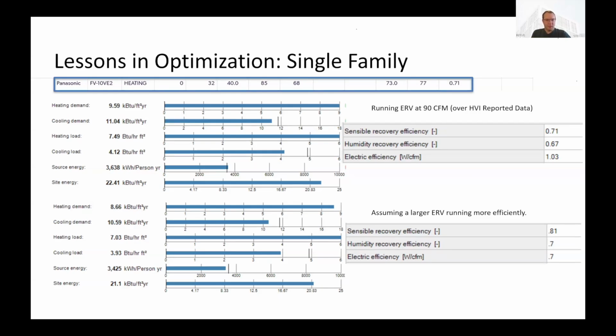What we did was even a little bit worse. So the airflow in this project was at 90 CFM, and maybe even should have been a little bit higher. So this is a well undersized ERV for this size of project. Typically, you want to look at running your ERV at maybe 50% or less of its max capacity. I'm a big fan of 40 to 50%, or maybe 40 is closer to the right number. In this case, we're running at like 90% of what the maximum capacity would be in this project. And that has a big impact on that sensible recovery efficiency by putting it down at 0.71. And I'll mention how I got there in a minute.